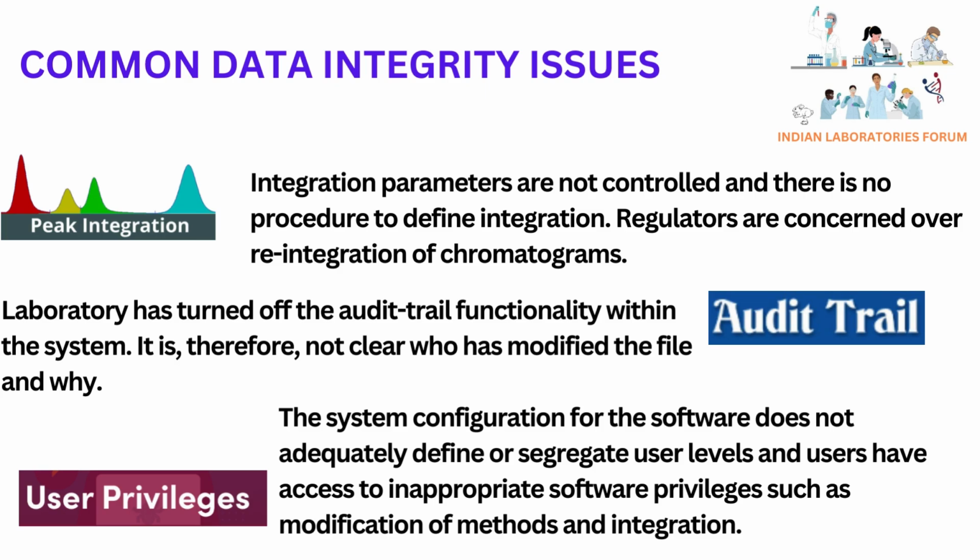Integration parameters are not controlled, and there is no procedure to define integration. Regulators are concerned over reintegration of chromatograms. The laboratory has turned off the audit trail functionality within the system. It is, therefore, not clear who has modified the file and why.